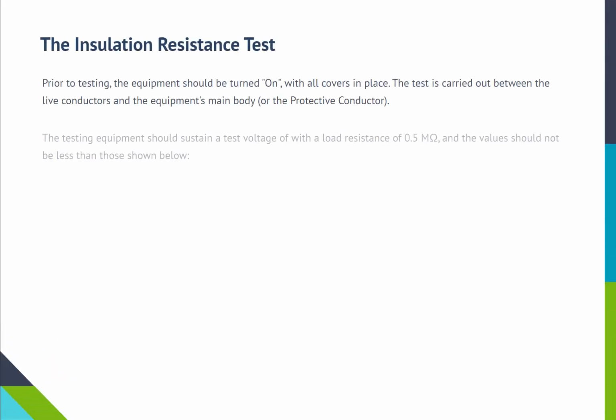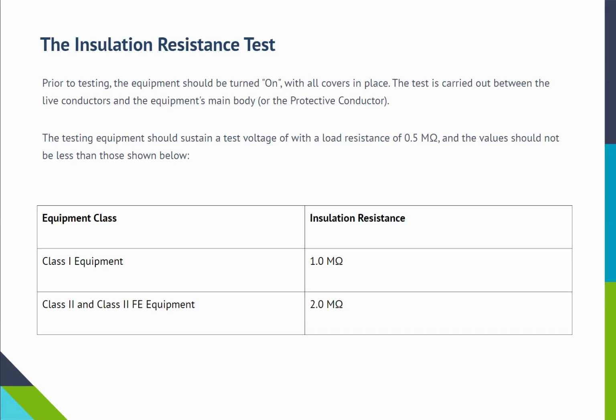Prior to testing, the equipment should be turned on, with all covers in place. The test is carried out between the live conductors and the equipment's main body, or the protective conductor. The testing equipment should sustain a test voltage with a load resistance of 0.5 megaohm, and the values should not be less than those shown below.